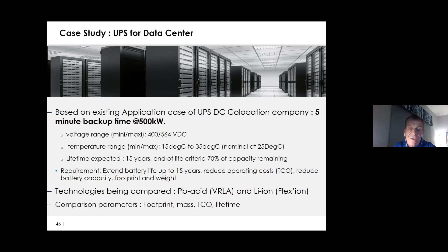The lifetime was expected to be 15 years with the end of life criteria with 70% of the capacity remaining. So we compared the VRLA batteries and the lithium ion batteries, the Flex ion. Here's what the results were of the actual testing itself. You can see that the high power lead acid batteries gave about 29 kilowatt hours. They had a 21 square foot footprint, which was twice as big as the lithium ion batteries. Look at the difference in weight, 13,000 pounds for the lead acid batteries versus 2,500 pounds for the lithium ion batteries.